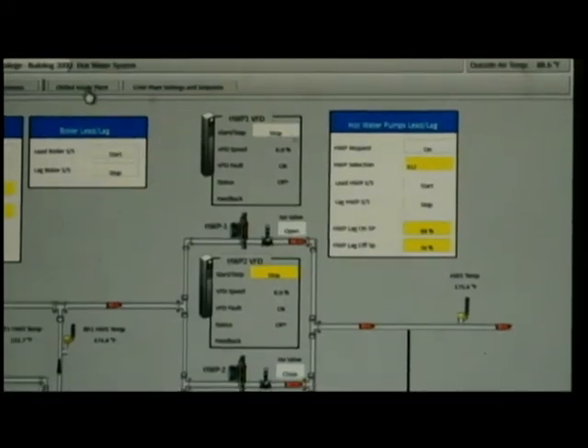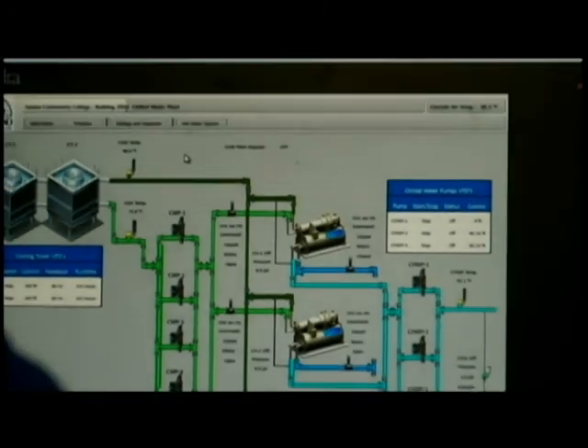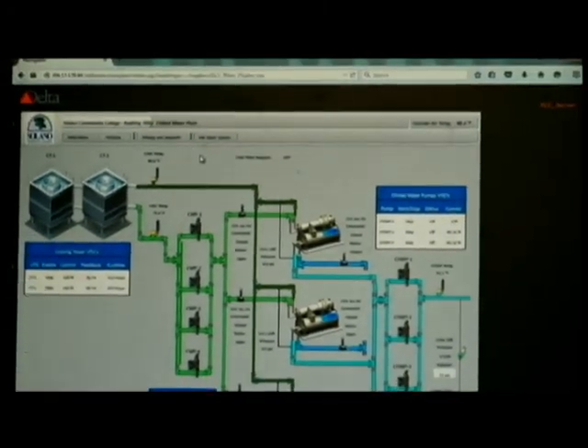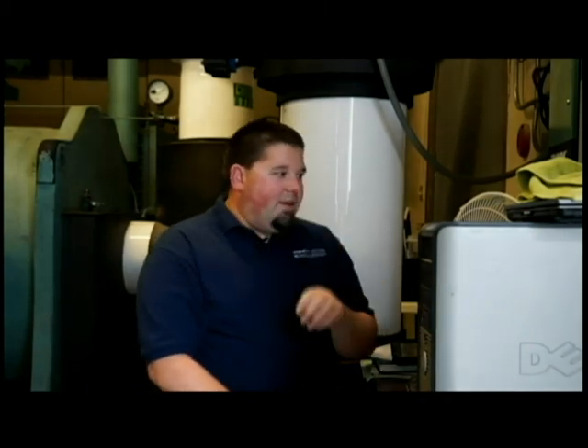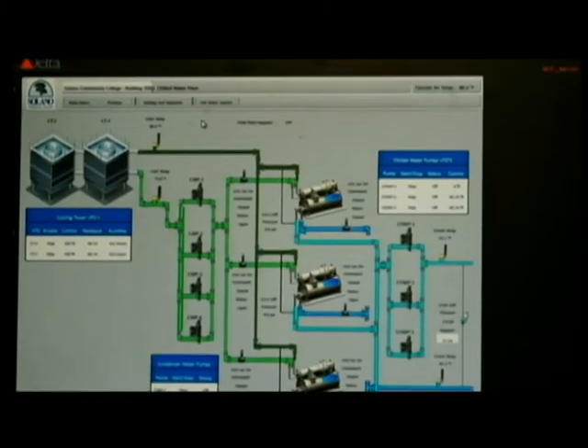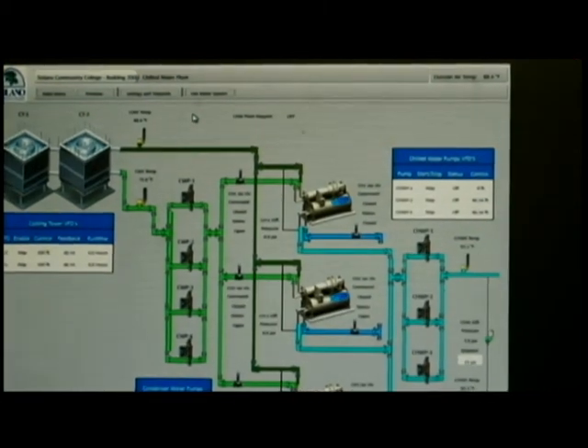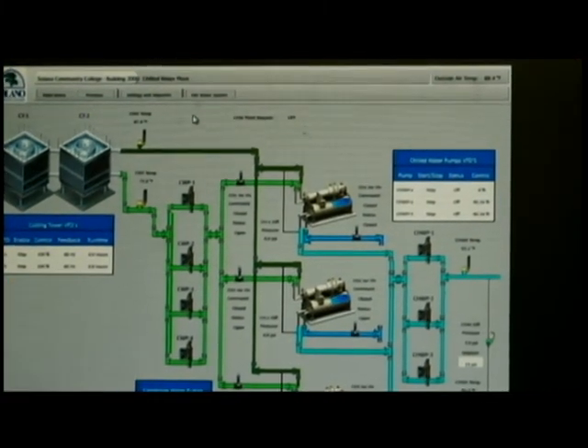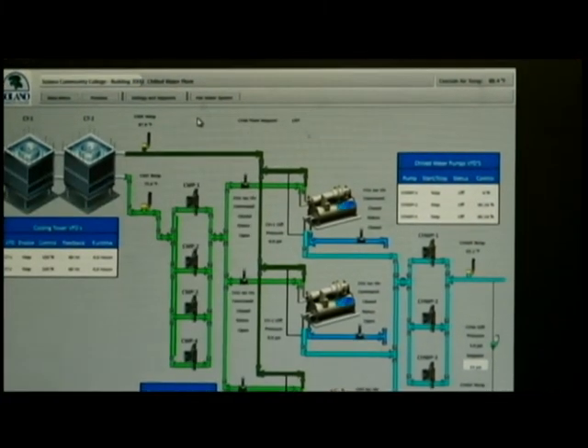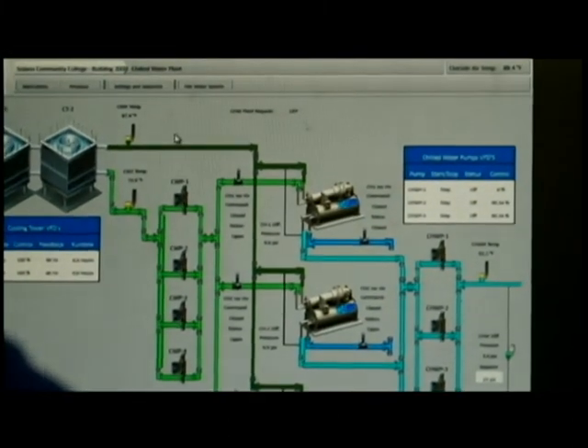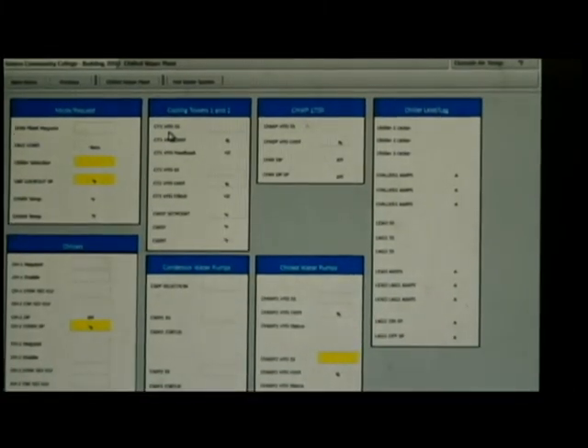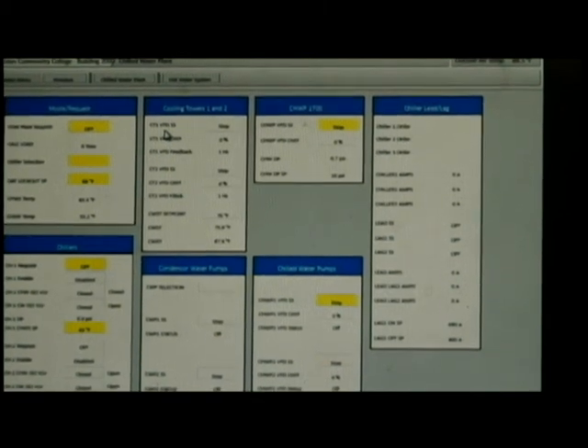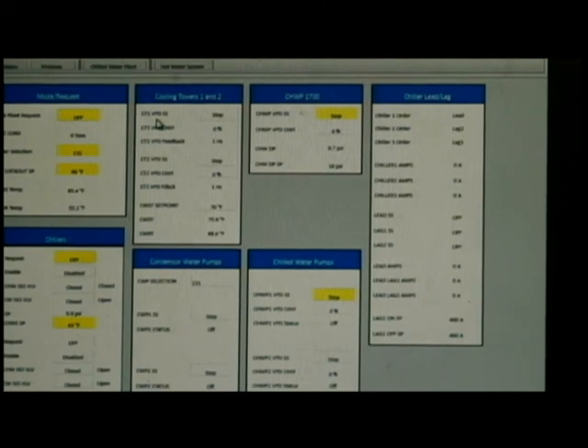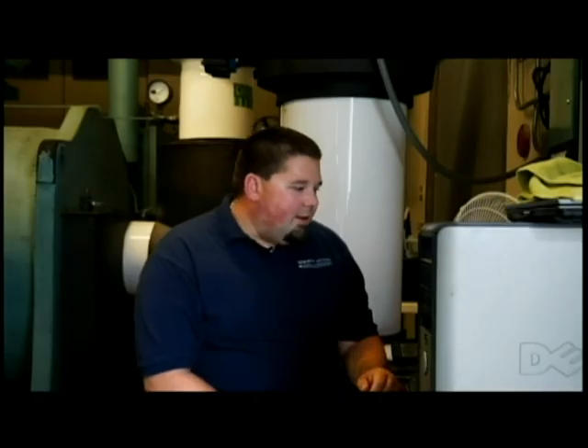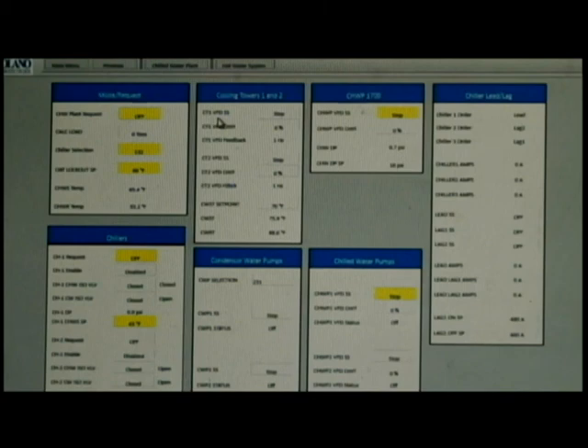The other side of things is the chilled water plant. So on the chilled water plant, as we mentioned, there's condenser water pumps and there's chilled water pumps, and they have lead lag capabilities as well as the chillers themselves. So we'll start off with the chilled water pumps. Taking a second to update in there. And I'm looking for the lag on because it's hard to read.